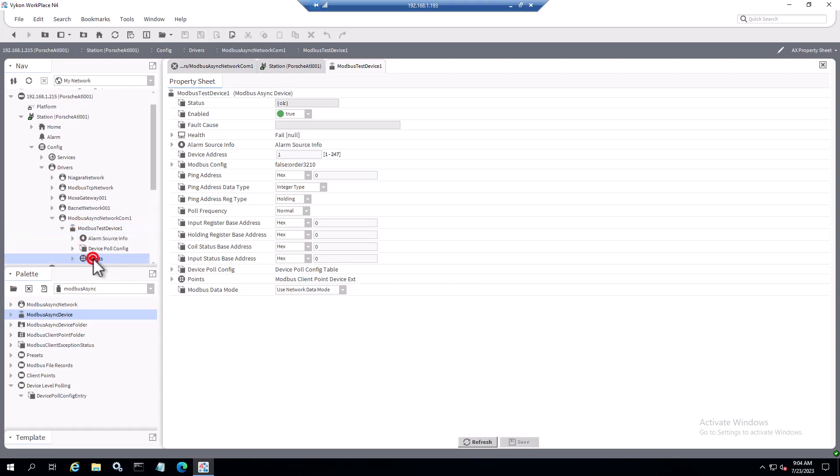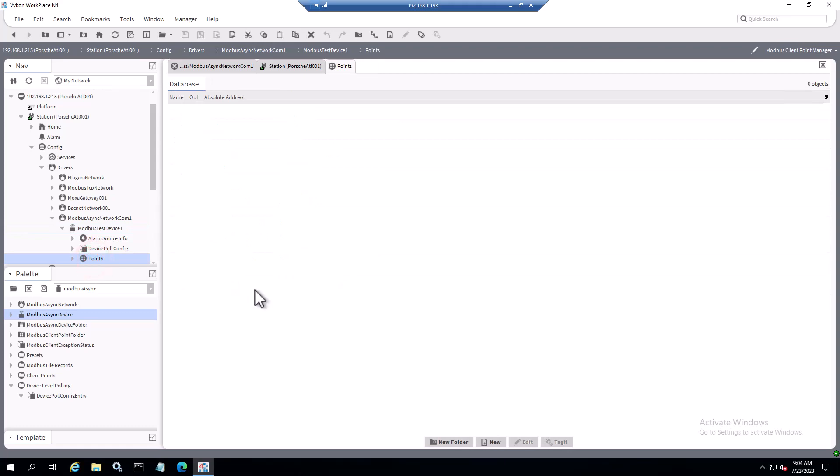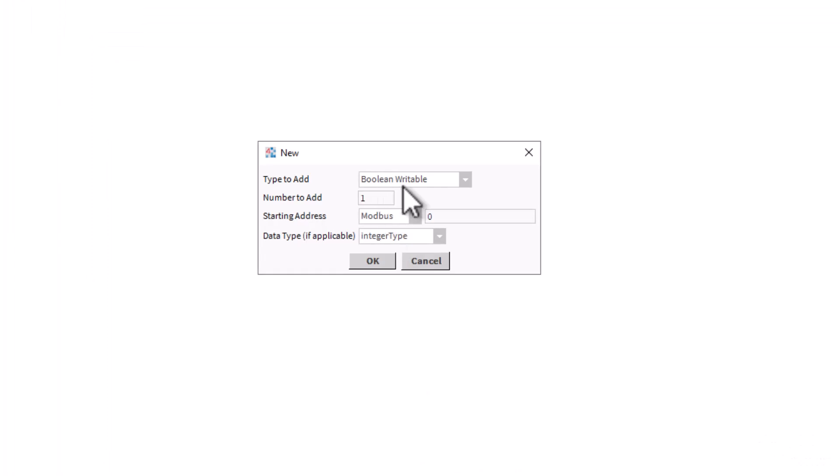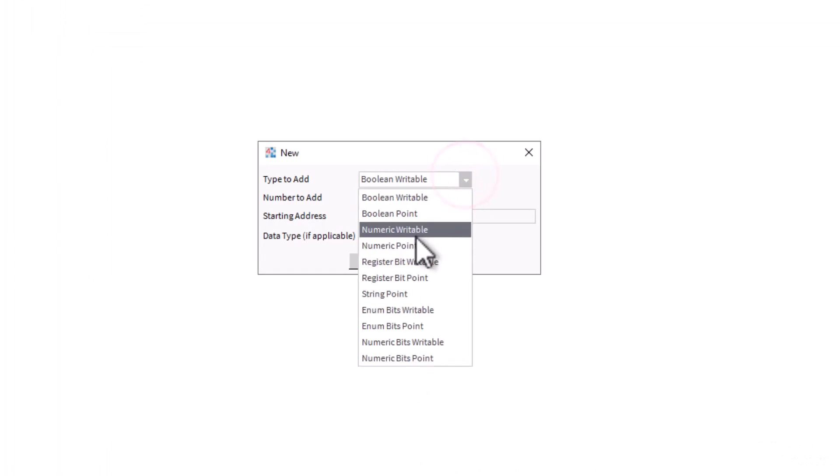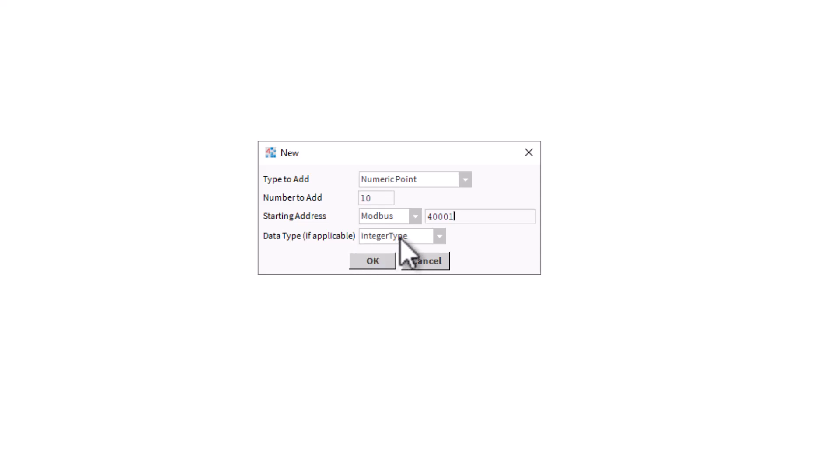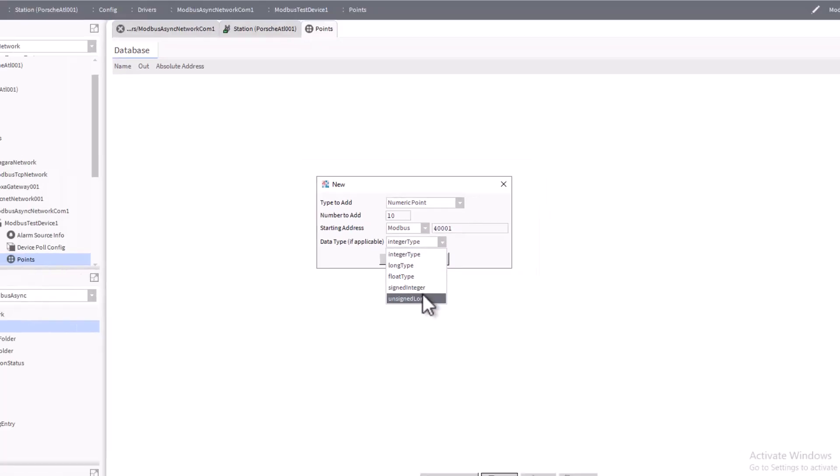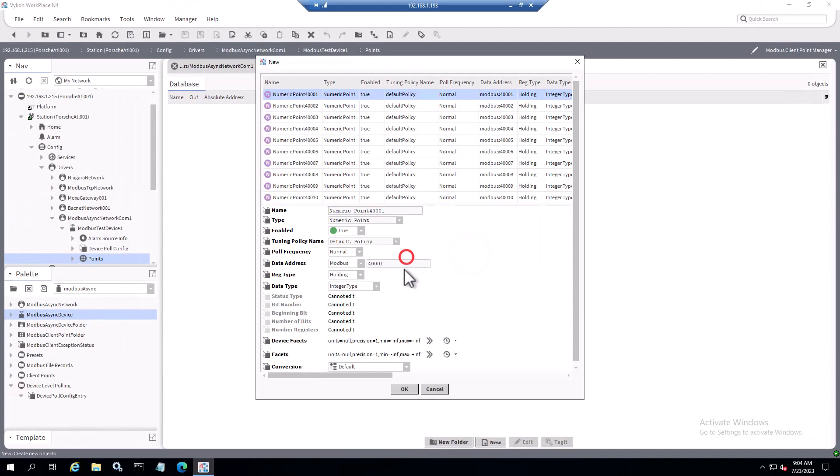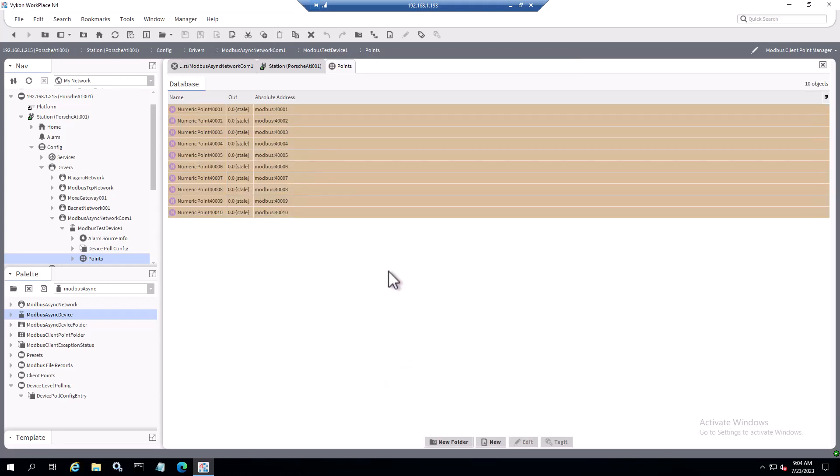Then we would just want to expand this, double click on points. It gives us a blank page. I'm going to add 10 holding registers just to test the port with. I'm going to select numeric point because on my simulator I'm going to be using Modbus holding registers 40001 to 40010. Number to add, go to 10 here. We'll go 40001 and then my simulator is going to be doing 16-bit integers, so we can just leave this set to the integer type. If you had something different or going directly to the device, just set up your profile accordingly. Click OK. We're not going to change the names on these because it's just for a quick test.